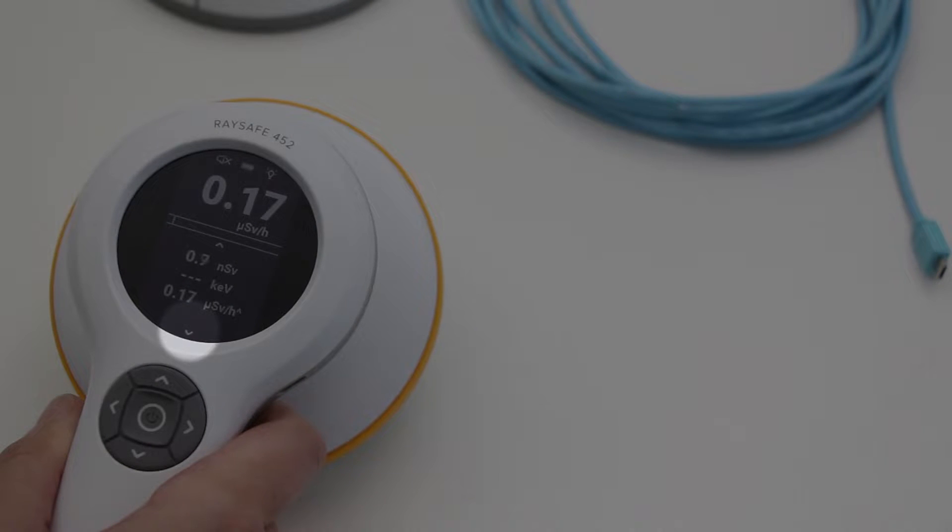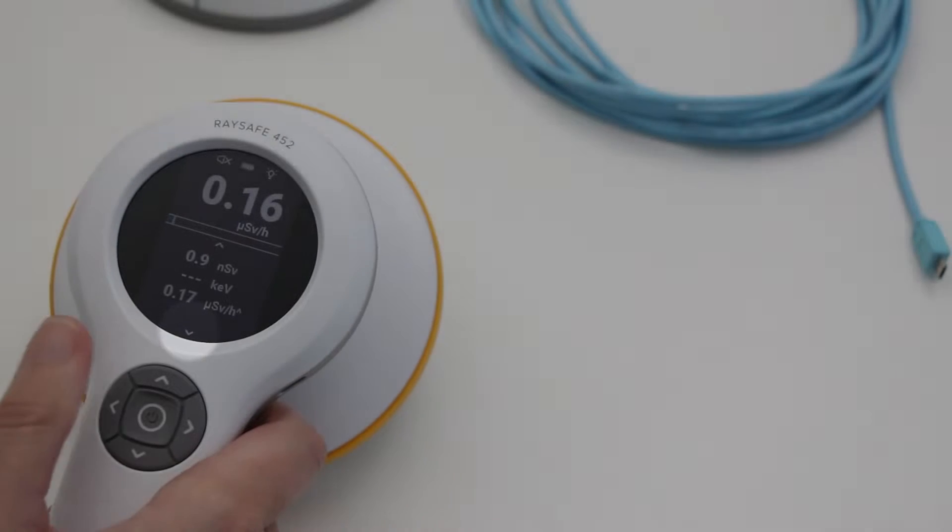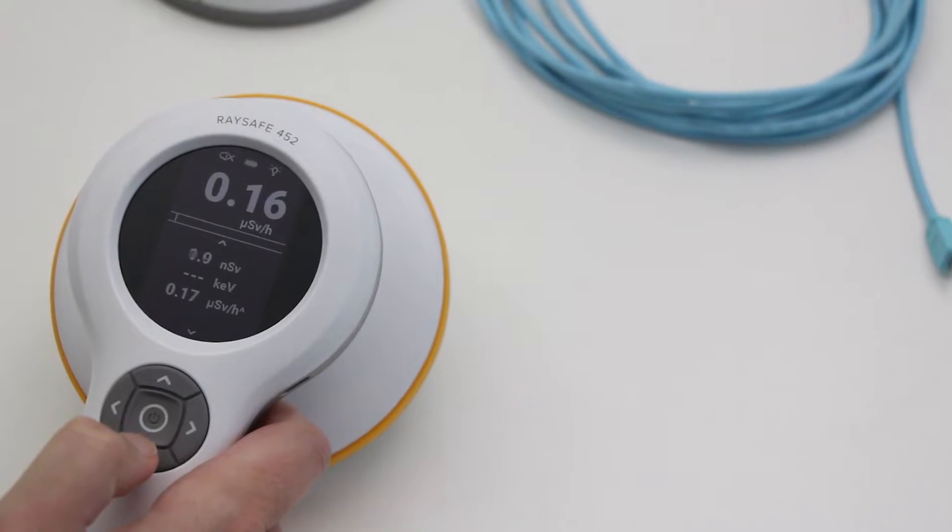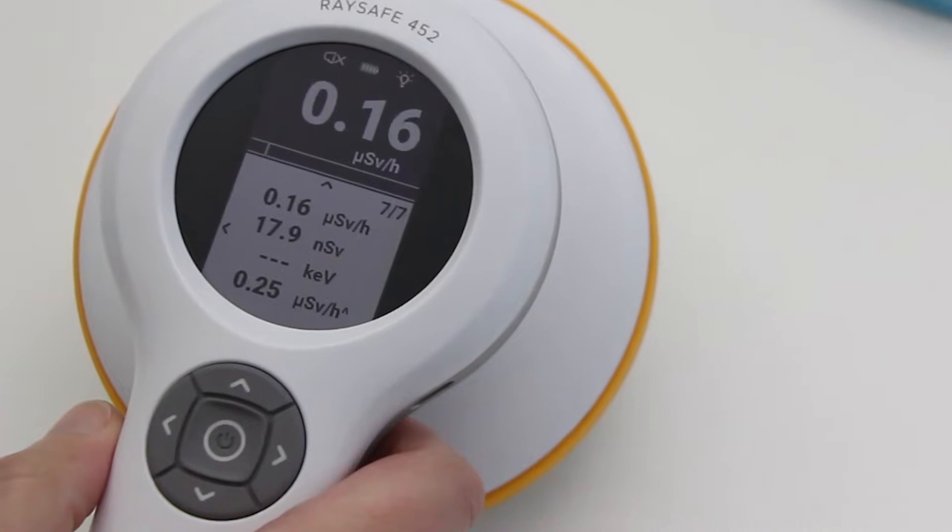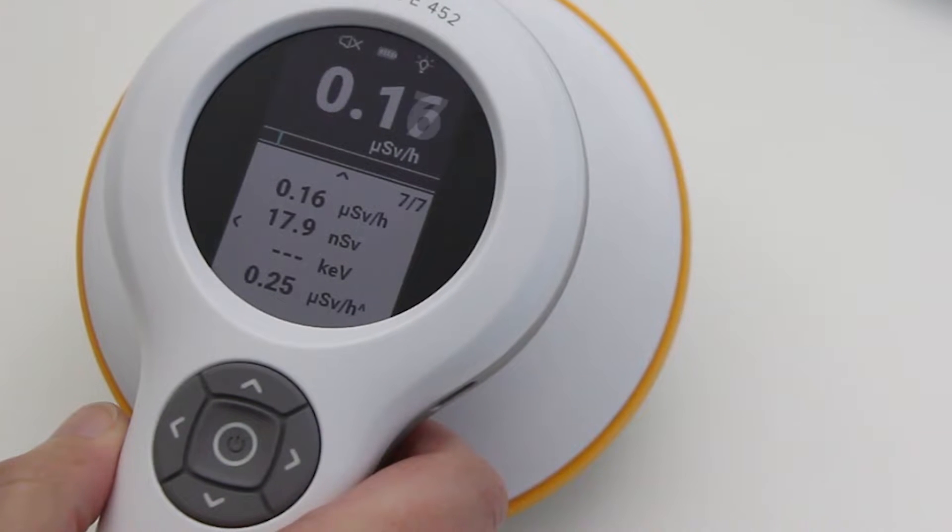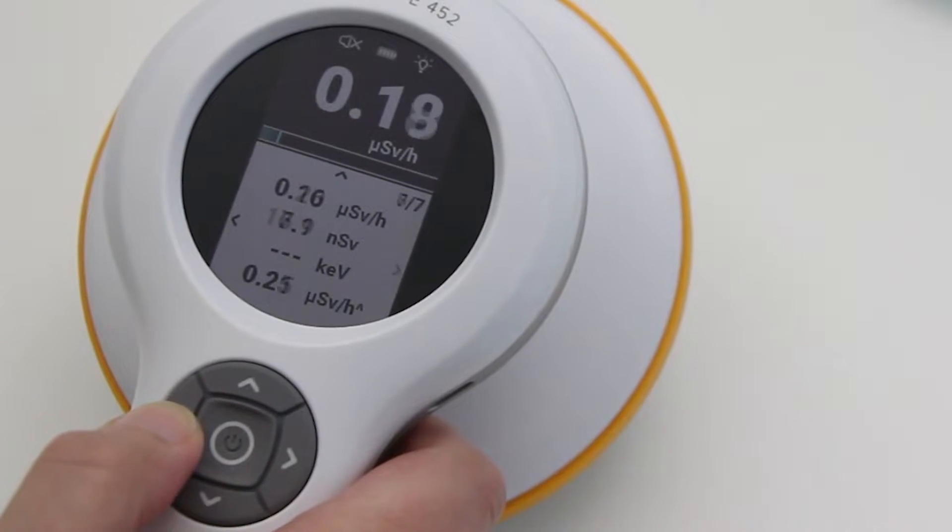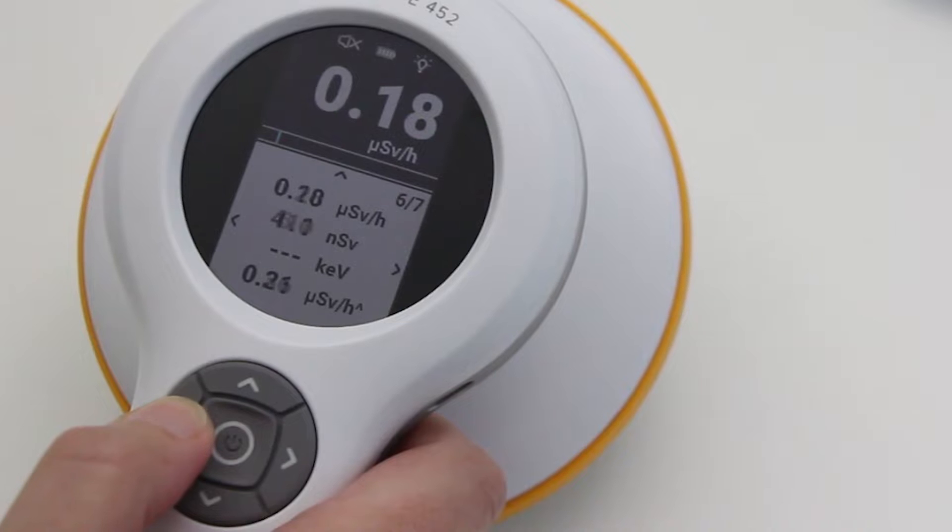The down arrow on the screen indicates that there are measurements stored since power on. Press the down button to take a look at them. The measurements are sorted in chronological order and you press left to see the previous measurements. All measurements stored since power on are visible here.